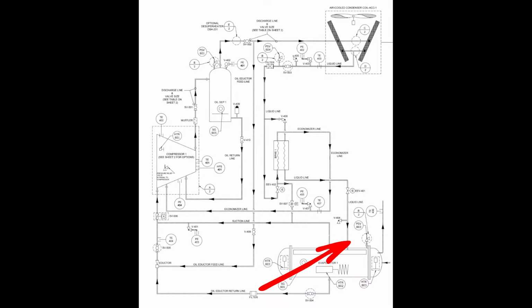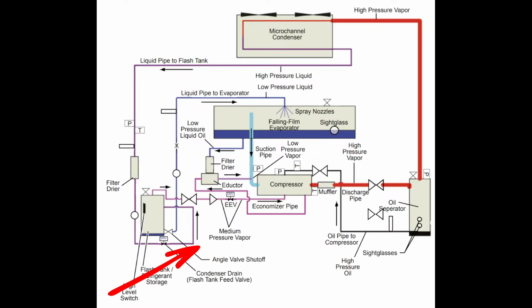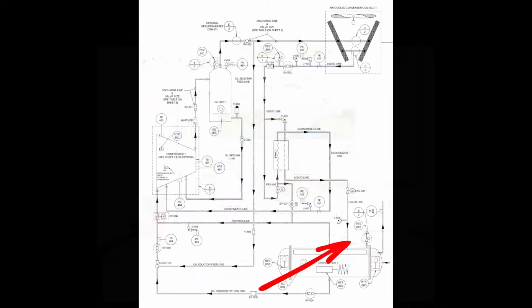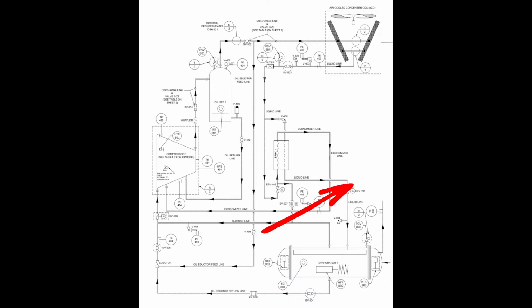Okay, so on the Style A, we had a drain valve, which is an EXV, and then a fixed orifice, right? So we had these two working in conjunction with the flash tank. With the Style B, we have a single metering valve leaving the economizer, then feeding into what they call a true hybrid falling film evaporator, which means that we're running higher liquid levels in the evaporator than we would normally run with a standard falling film. So it's the same exact style that you would see on like a YK centrifugal, if that's something you've serviced.